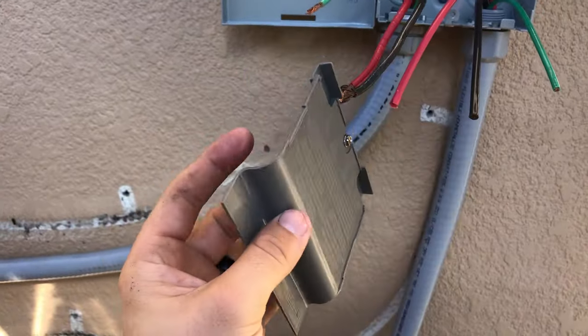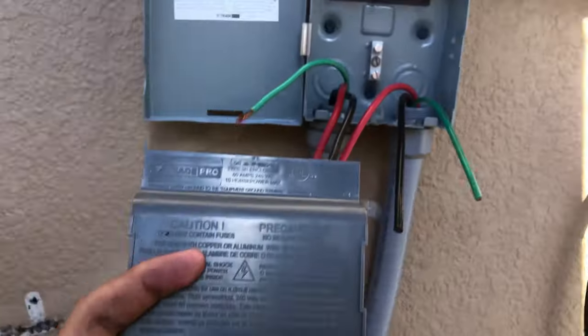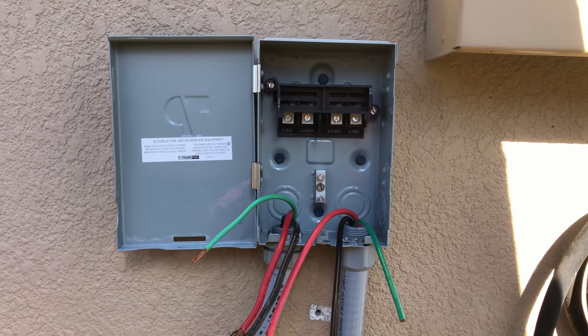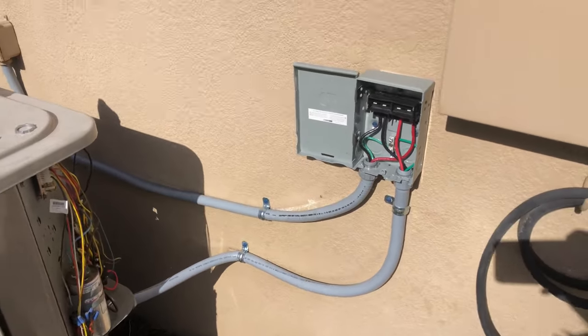What's interesting is the actual panel label tells you, depending on the wire size, how much torque you should be putting on those lugs. If you have a torque screwdriver, that's a nice tool to have. So we'll go ahead and wire this up — and we've got the disconnect all wired up.